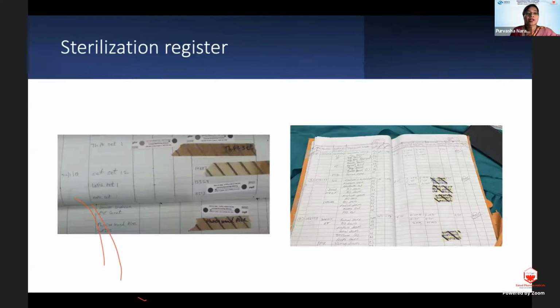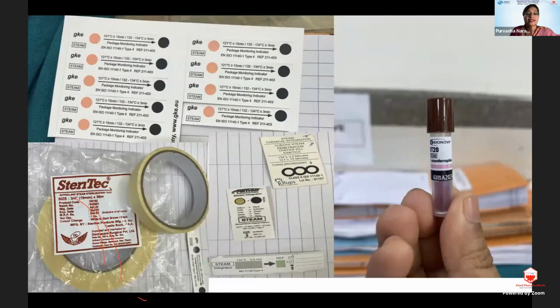And this is the typical sterilization register which has to be maintained. You have to place these strips along with the indicators, mentioning the date, the time, the lot, the name of the technician, the name of the in-charges. Everything has to be mentioned serially. These are the various types of indicators used. And for batch monitoring, we can use the Bowie-Dick test before sterilization in the morning of all the autoclave processes taking place. And once a week, you should also put in the biological indicator to know the efficacy of the system.